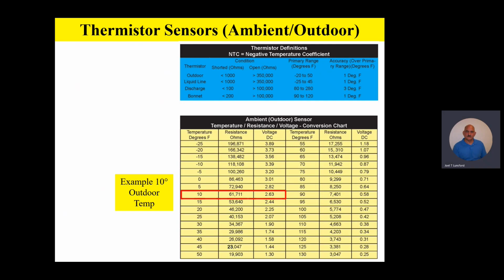So in this example, if we know it's 10 degrees outside because we measured the outdoor air temperature, and we remove the sensor from the board, and we take an ohm meter and we ohm out that sensor as we remove it off the board, it should be 61,711 ohms. Or on a digital ohm meter, it'll read something like 61.7 K, 61.7 K ohms. And so depending on the type of meter you have, if you have an analog meter, you'll have to look at the meter and extrapolate it: 61,711. Or if it's a digital ohm meter, it may read 61.7 K. You get the idea. So basically, the resistance of that outdoor ambient sensor at 10 degrees should be 61,700 or very, very close to it.